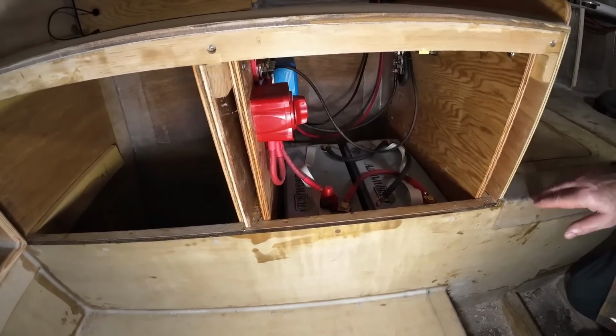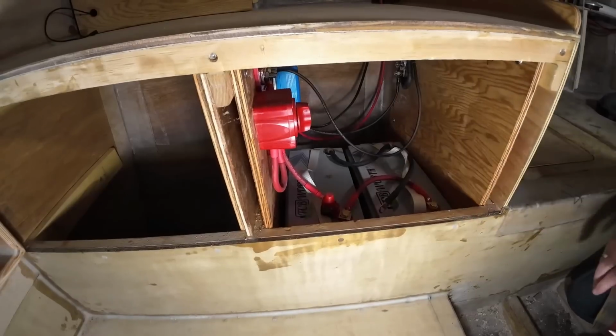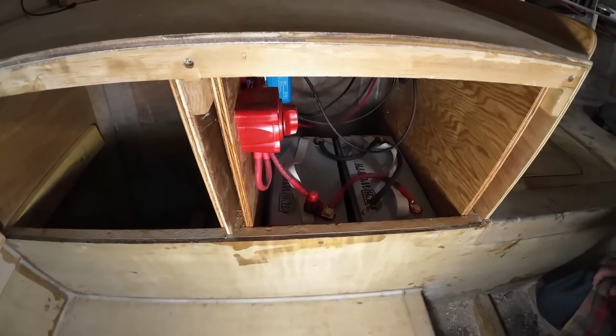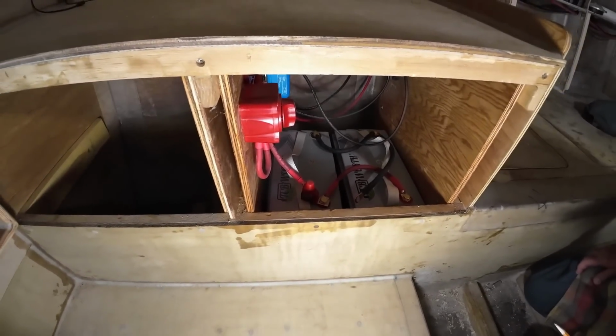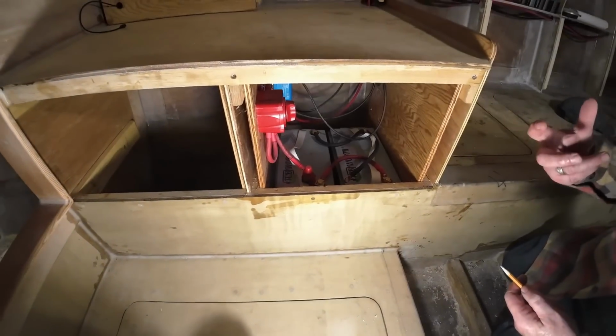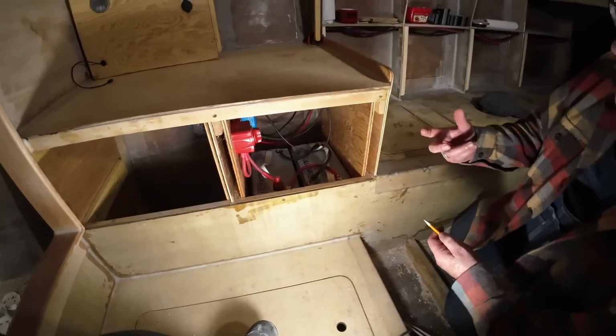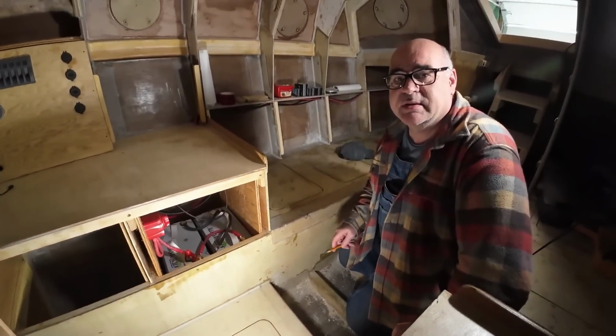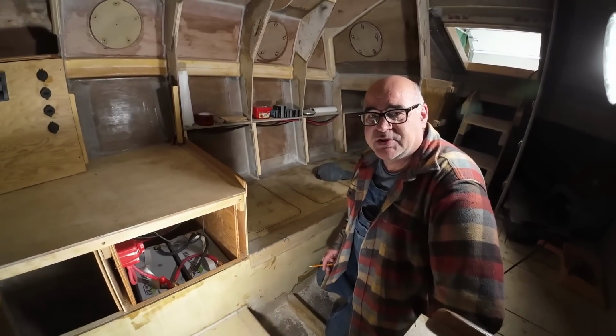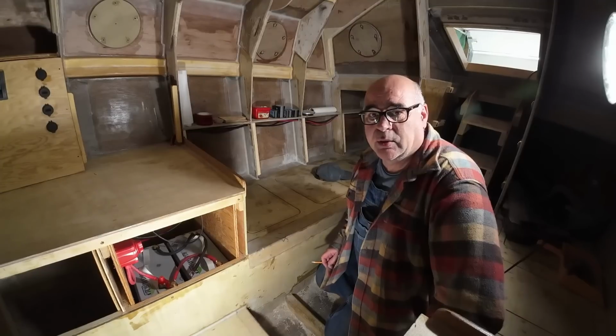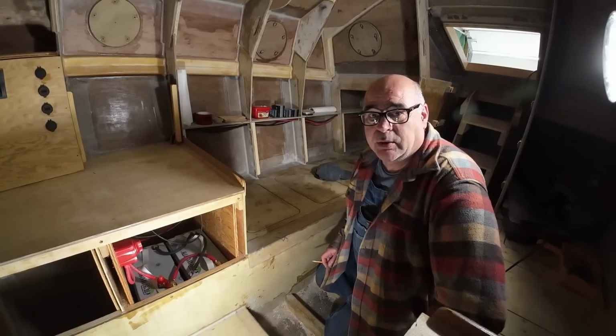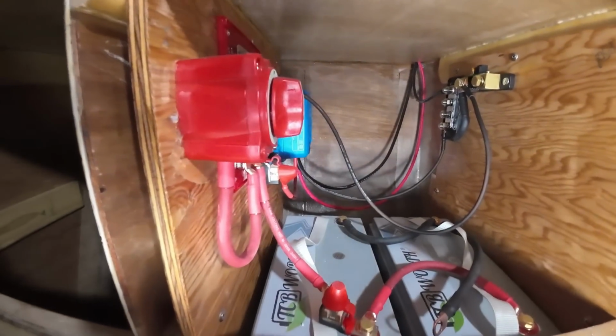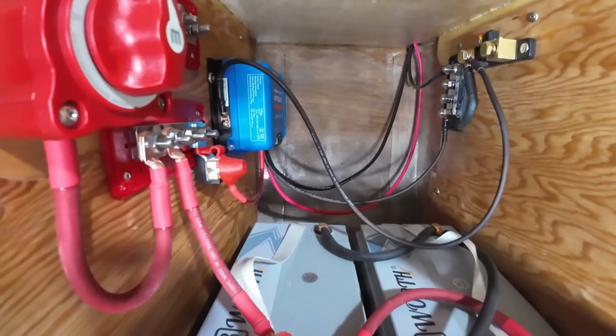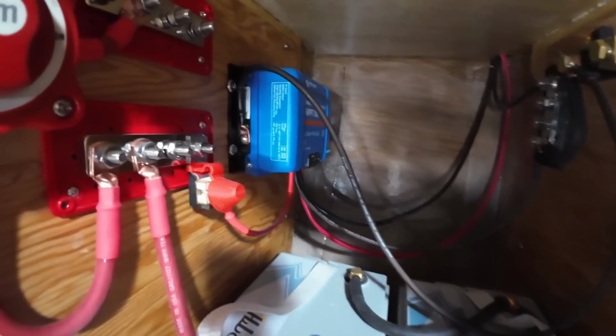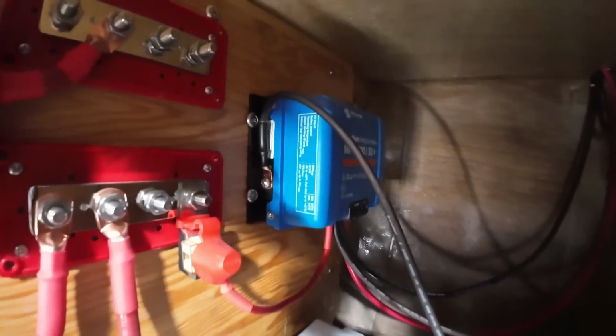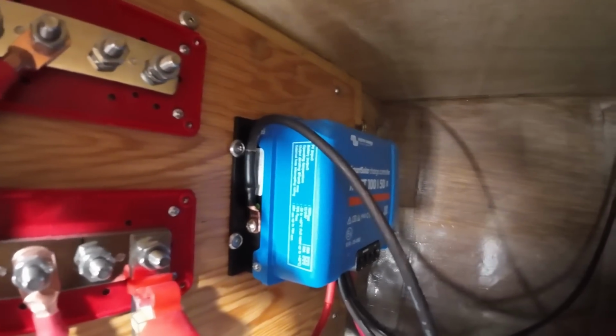Yeah, so for the major battery cables, we're using 2 AWG gauge, which is a heavy-duty cable, and the idea behind how much electricity you're using through wires is to ensure that you're able and capable of handling the load. Too much load and you basically turn your wires into a toaster, and that's where electrical fires start. So appropriately sized wires with the lugs and connections will prevent electrical fires.